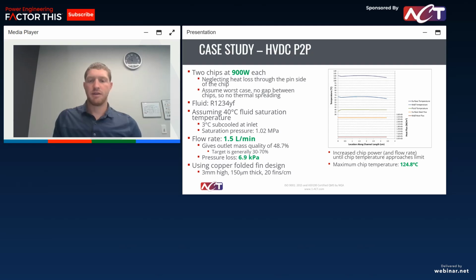And then for our analysis at 900 watts, the higher 300 watts per centimeter squared watt density, the flow rate had to be increased up to 1.5 liters per minute, but you were able to keep that chip temperature below the limit there. You're at 124 C. That was the chip temperature, which I think is what they're looking for in terms of operating temperature.